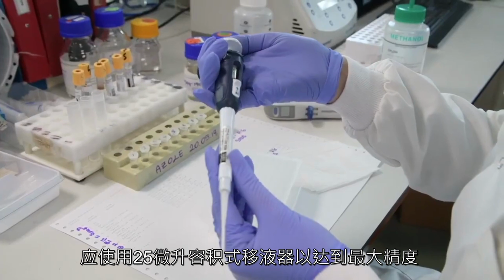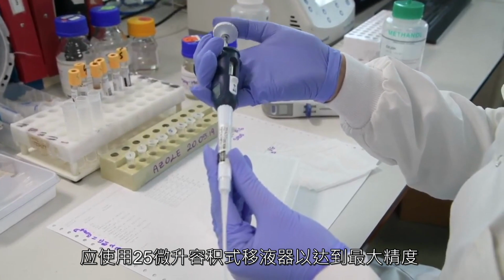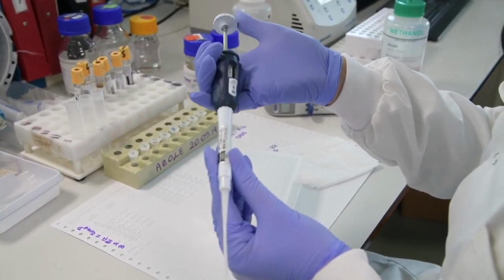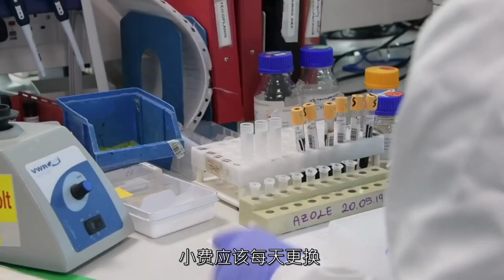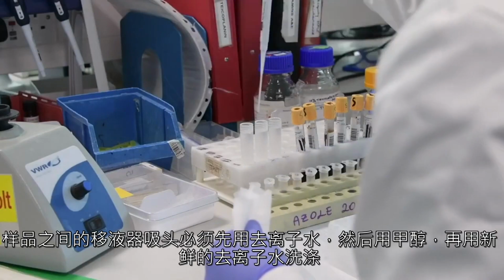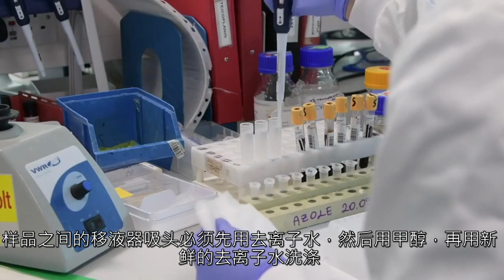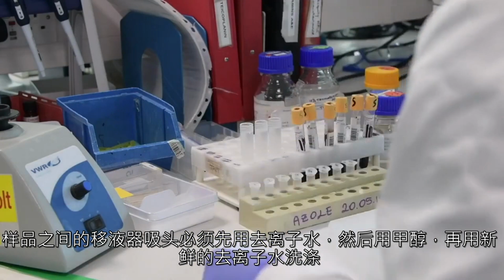A 25 microliter positive displacement pipette should be used for maximum accuracy, and the tip should be changed daily. The pipette tip must be washed between samples with deionized water, then methanol, then fresh deionized water.